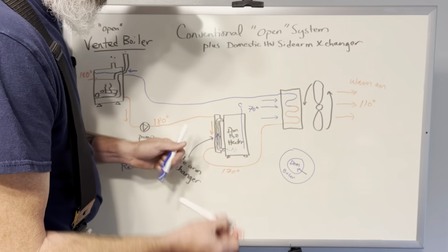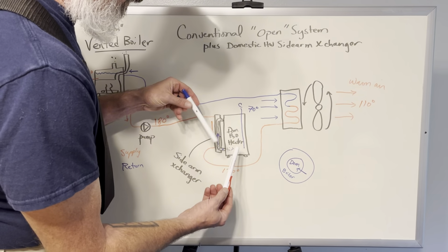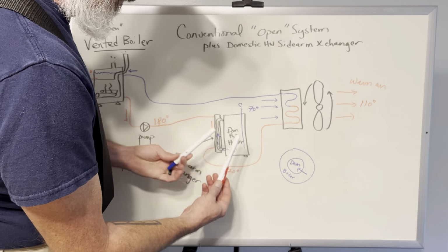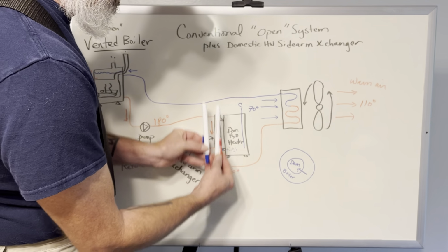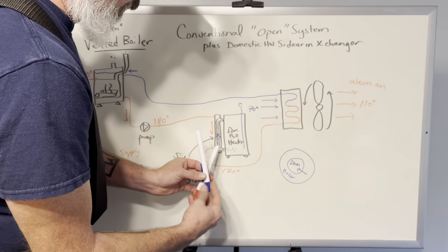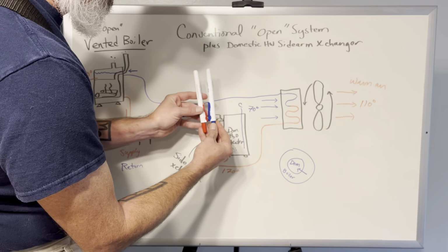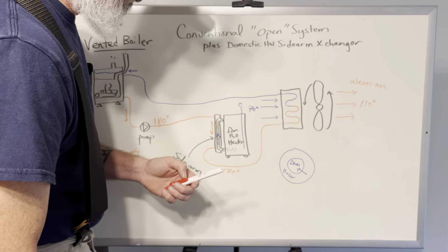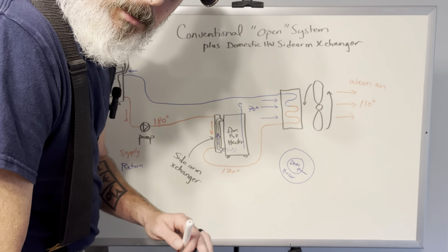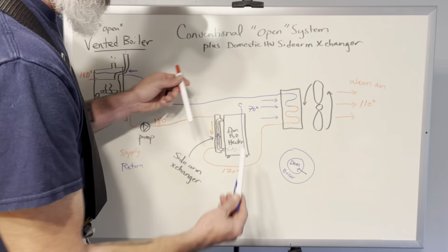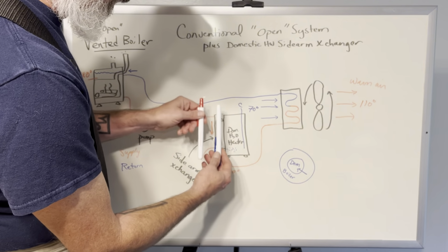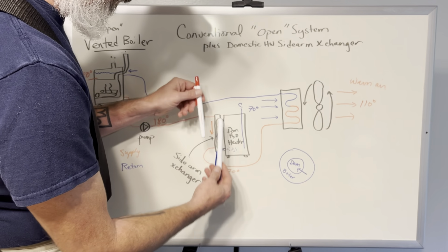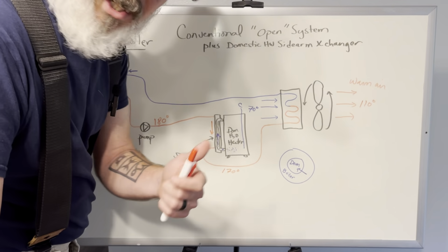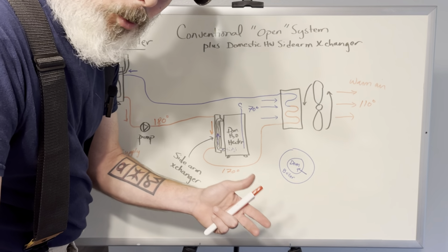And I've rarely seen a scenario where going parallel flow, which would be like that, the cold and the hot running side by side, will net you better heat transfer. So in general, when in doubt, always pipe counterflow with any kind of heat exchanger. That's air to water, water to water, oil to oil.